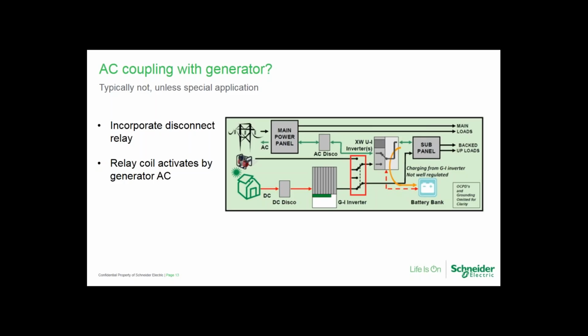So anytime that generator is called upon to start, it's going to be because the batteries are low, typically. And so we want to make sure that the grid tie inverter is disconnected so that we don't run into a situation where the batteries are charged and the PV exceeds the load demand. It has nowhere else to flow but back to the generator, and that typically would not be a good thing.